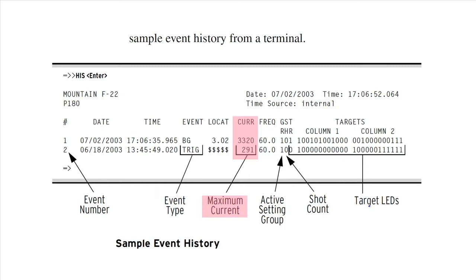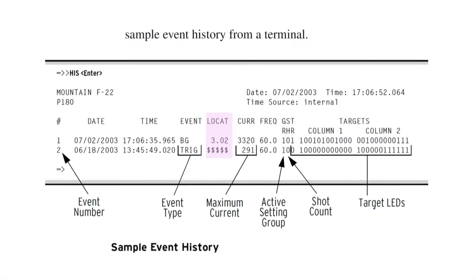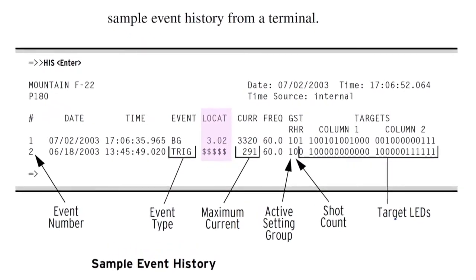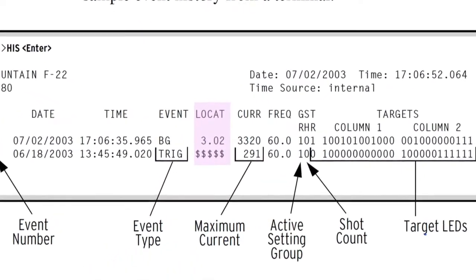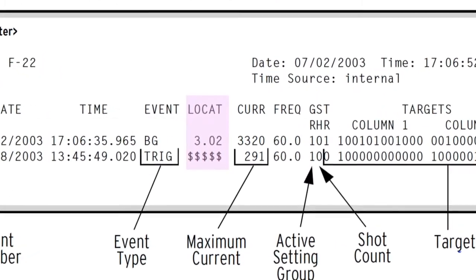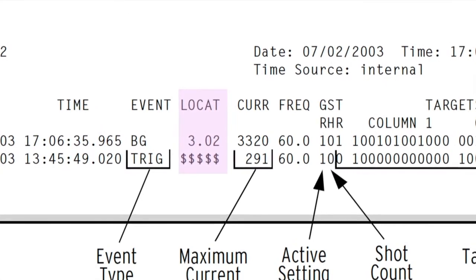The identifiers, date, and time information is at the top of the standard event report, and the other information follows at the end. The event field shows the event type. The event type designations AG through CAG are only entered in the event field if the fault type is determined successfully. If the fault type is not determined successfully, just trip or ER is displayed. Fault location. The recloser control reports the fault location if the EFLOC setting equals Y, and the fault locator operates successfully after an event report is generated.